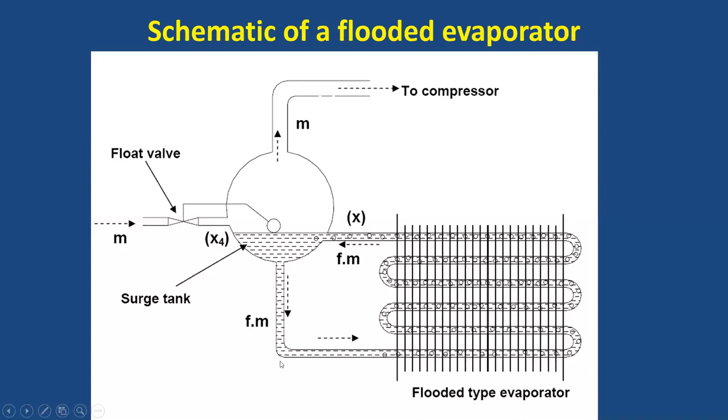But this type of evaporator is more effective. Here the refrigerant is fully utilized, because till the end the latent heat is used, and not a single bit of vapor is superheated in this case. So the entire latent heat is utilized here. So obviously the thermal performance of the flooded evaporator is more.